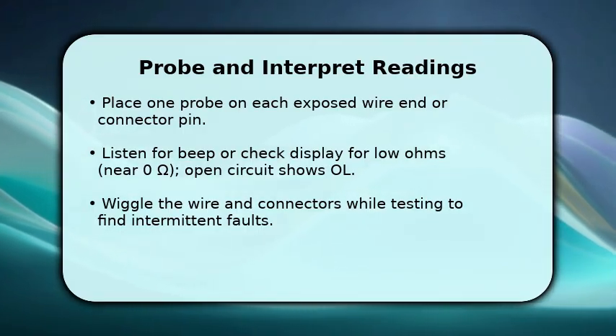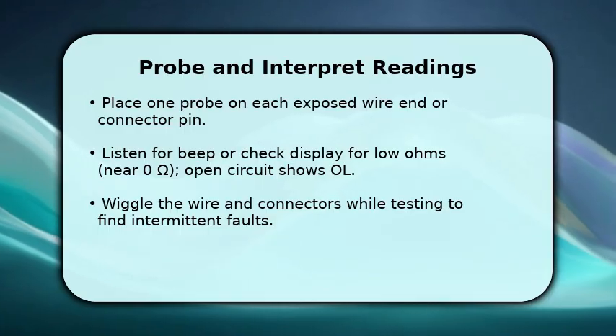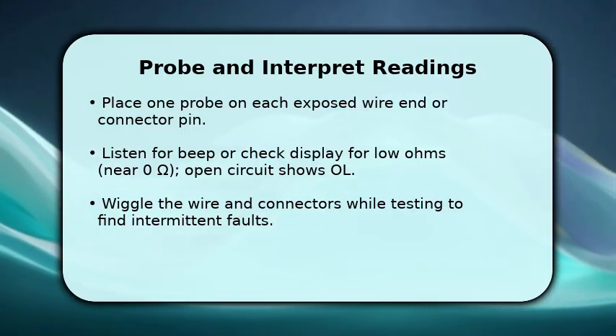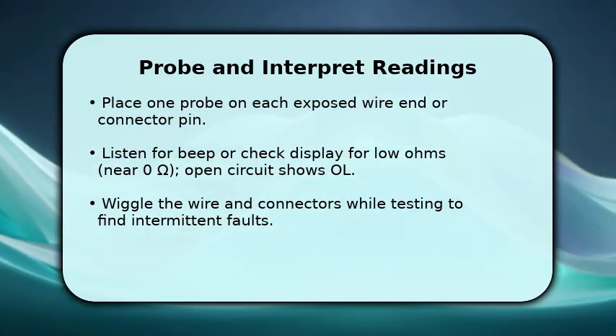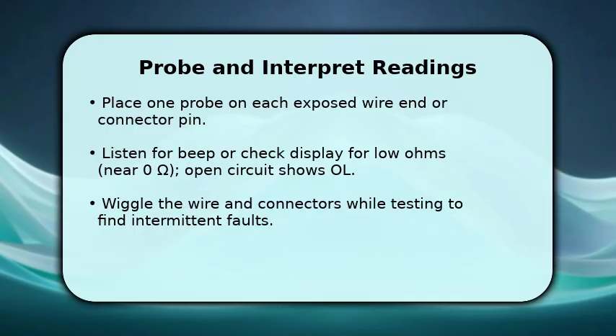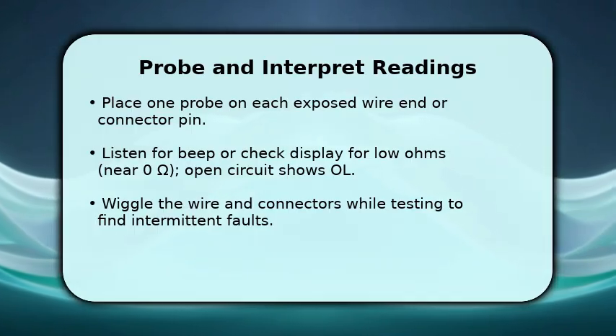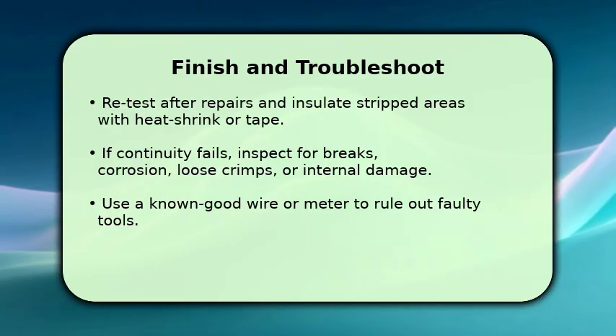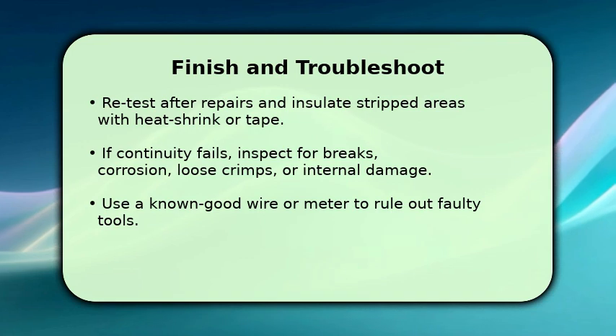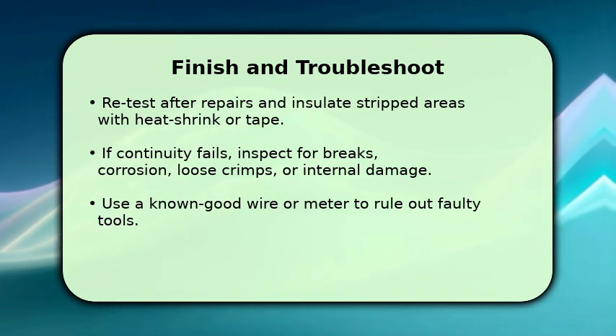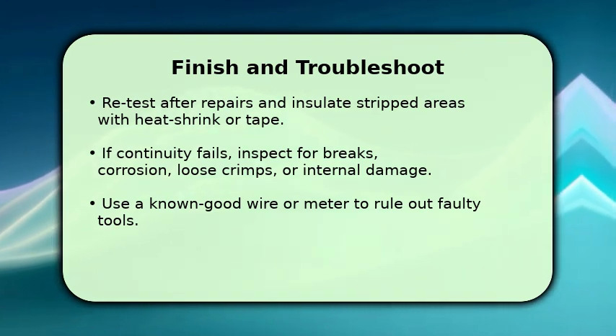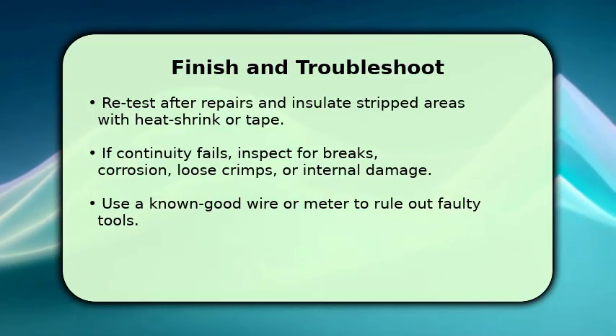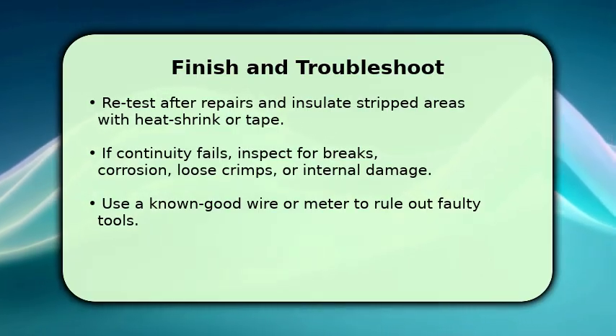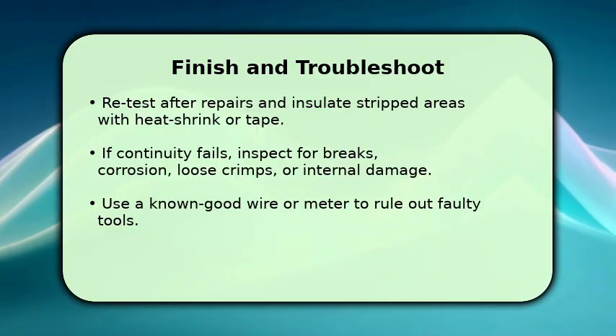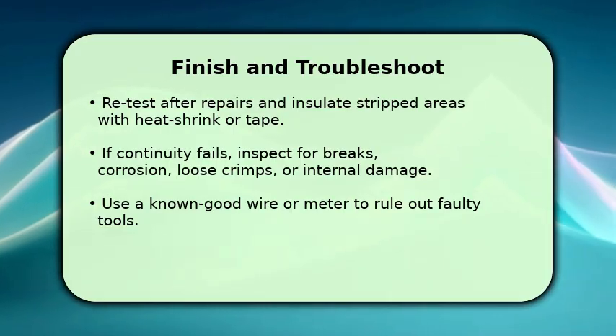While holding probes, gently wiggle the cable and connectors to reveal intermittent breaks or corroded contacts. That helps locate damage that only appears under stress. When you finish, recheck continuity after any repair and insulate exposed metal with heat shrink tubing or electrical tape to prevent shorts. If you still get no continuity, inspect the entire length for visible breaks, kinks, or corrosion at terminals and crimps. Replace the wire if internal copper is fractured.